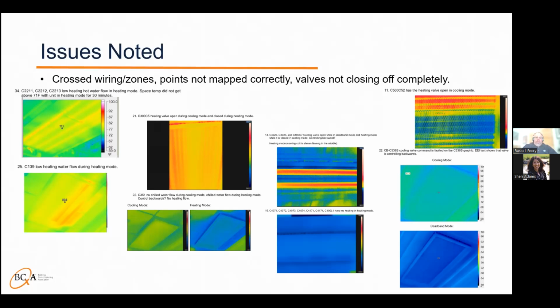Issue number 21 there, the heating valve was open during cooling mode and closed during heating mode. That was just some valve signals that were swapped that would have been caught had they done some pre-testing with an infrared camera. The next one we had kind of the same thing, the one right below that, issue number 22, no chilled water flow during cooling mode. And we had chilled water flow during heating mode.